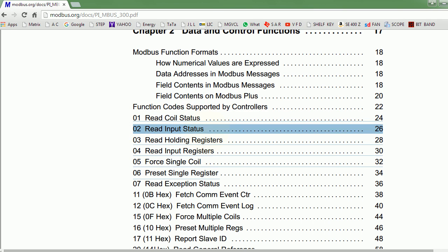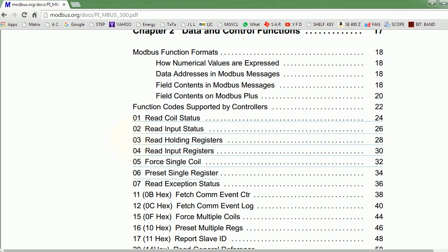Function code 03 covers holding registers, which are Modbus registers that by default are 16-bit wide. Holding registers are read-write - this is typically your analog output, which you can both read and write. Input registers are typically what are called analog inputs in the PLC world or in the industry world. You cannot really set these values from the master side.